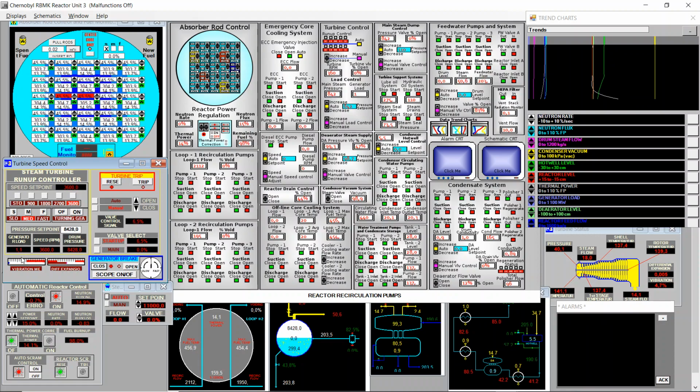So now we are at 1 megawatt. We don't have any more danger of reverse power. And now I will switch to auto. Switching to auto will automatically open drastically more the startup valve, and you see the generated load increasing much more now. We're at a power set point of 8600. We don't need that much, so I will manually decrease to 7500.